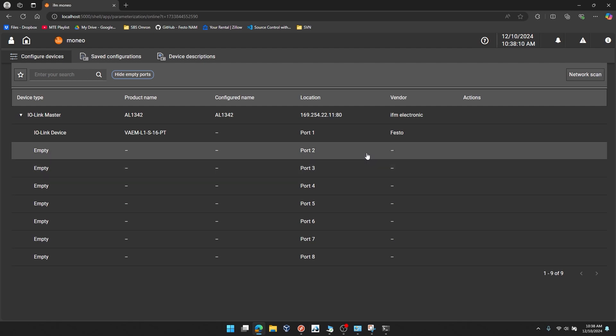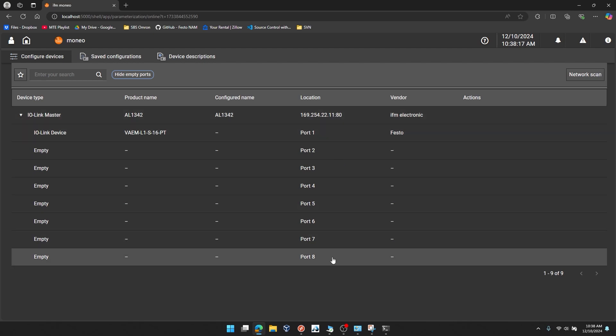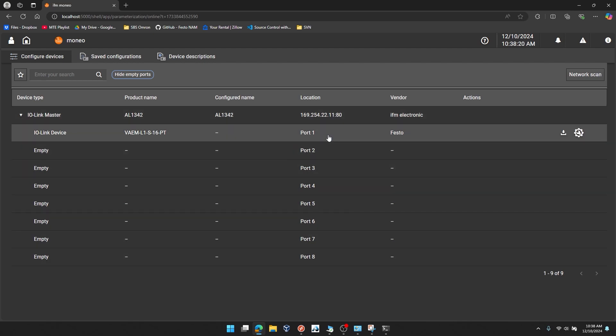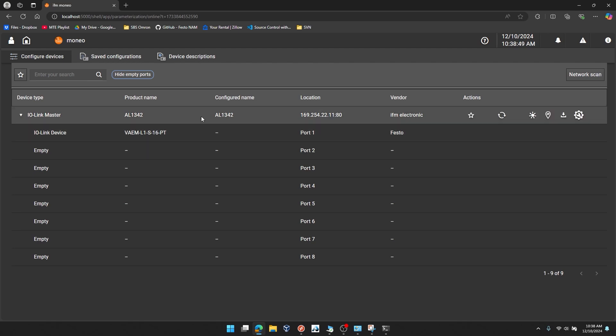So you can see right away that in Moneo here, I have my AL1342. It has eight ports for IO-Link devices. And at port one, the very first port again, I'm already detecting the IO-Link interface. So note this is the IO-Link interface VAEM-L1S16 for 16 valve positions up to 32 coils. And it's detecting that device with the embedded IO-DD that is found under the device descriptions tab. I did not have to install that IO-DD for this to work. It's just pulling that value from the online repository of IO-DDs.